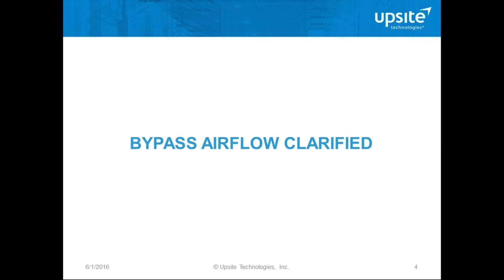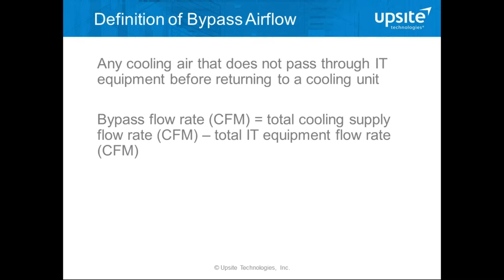One of the most fundamental concepts is bypass airflow. It's widely known but not widely understood. The definition is simply any air that comes out of a cooling unit that does not pass through IT equipment before returning to a cooling unit is bypass airflow. A lot of people think that by installing a blanking panel or sealing a cable opening they're affecting the bypass airflow — that might be true at the rack level, but it's not true at the room level.